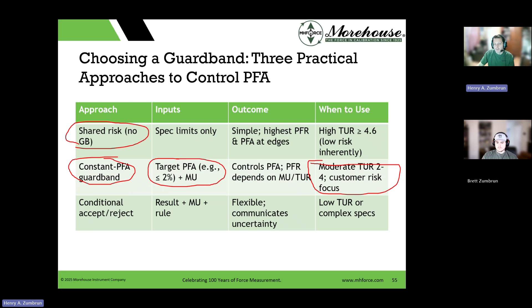And then you have conditional accept/reject result plus the measurement uncertainty plus rule, for low TUR and complex specs. So just when you could use it, you don't have to. It all depends on your likelihood and consequences. Guard bands do not reduce your measurement uncertainty. They define how we use uncertainty in measurements to make conformity decisions and allocate that decision risk, producer versus consumer. A better measurement process is the most direct way to reduce both risks, but a documented decision rule is still required whenever a statement of conformity is made.